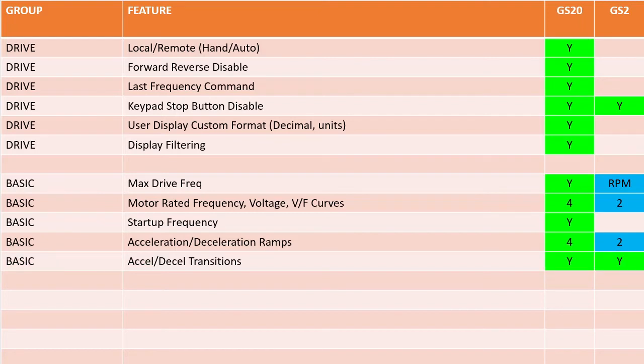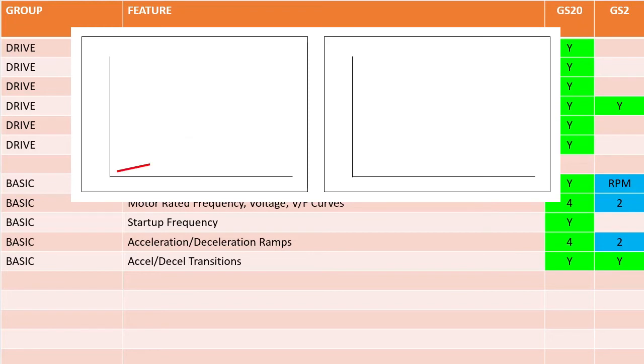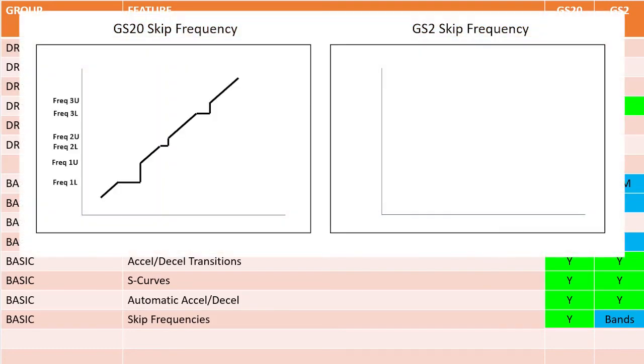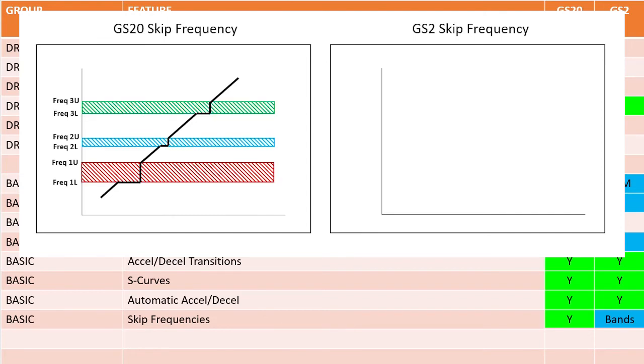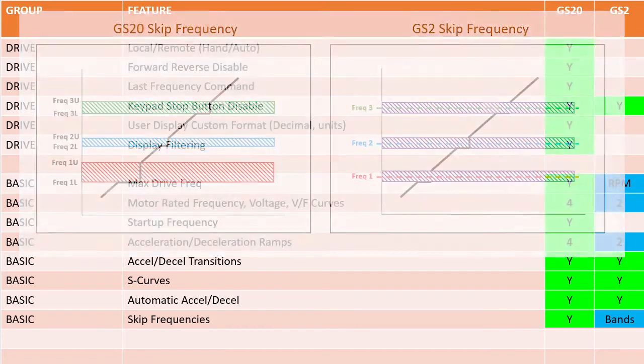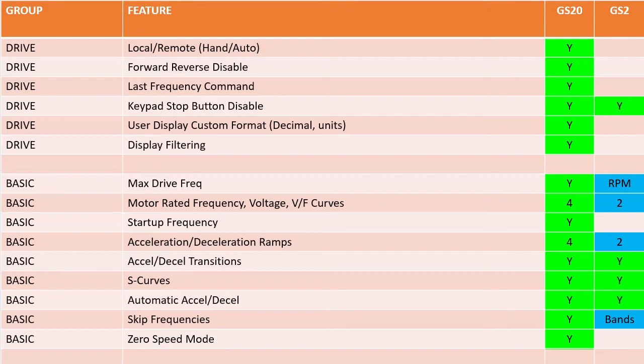Both drive families have acceleration and deceleration transitions so you can have one acceleration time during one part of the ramp and another during the second part — maybe accelerating slowly at the start to prevent overcurrent issues and then speeding up, or quickly getting close to speed then slowly approaching the final speed. Both families also have S-curves to smooth out transitions and options to automatically give you the fastest possible acceleration and deceleration times. The GS20 has upper and lower skip frequencies so each skipped frequency band can be unique, whereas the GS2 applies a single skipped band to all skip frequencies. The GS20 allows you to specify how the drive reacts if a frequency below the minimum allowed is requested — should it do nothing, apply a DC brake, or continue using the min frequency. And finally, the GS20 has regen options to give you more control over deceleration.